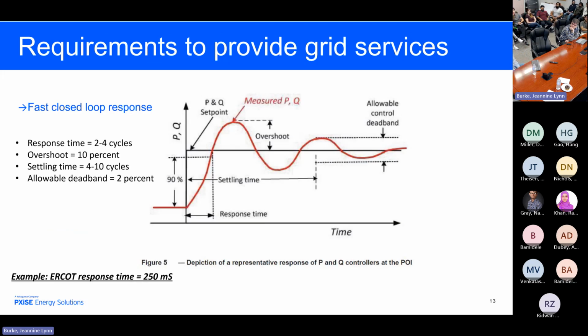This is just a quick summary of what we mean by the closed loop response of the microgrid. By the way, this is right out of the IEEE standard 2030.8, the testing standards. Typically, with ERCOT, for example, if you want to participate in the fast frequency response at ERCOT, you have to show that you can do a set point change in 250 milliseconds. That's slower than 4 cycles, but I think we can make a 4-cycle one as well. Faster is better in the electric power grid, is our thesis. So basically, we want the closed loop control system to have a response like this.